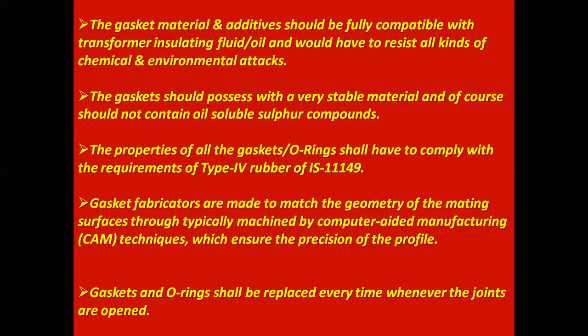The gasket material and additives should be fully compatible with transformer insulating fluid or oil and would have to resist all kinds of chemical and environmental attacks. The gaskets should possess a very stable material and of course should not contain oil soluble sulfur compounds. The properties of all the gaskets or O-rings shall have to comply with the requirements of type 4 rubber of IS 11149.